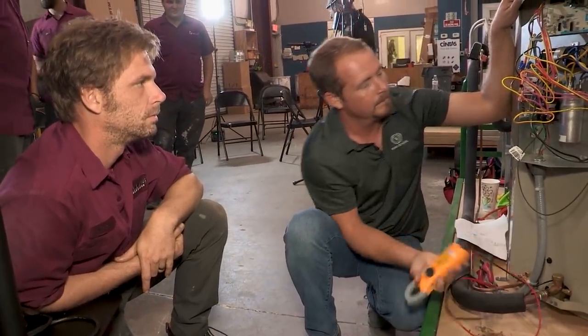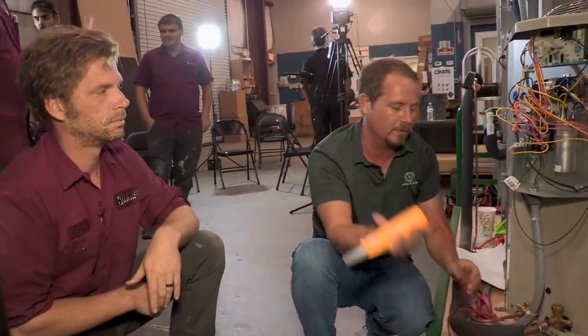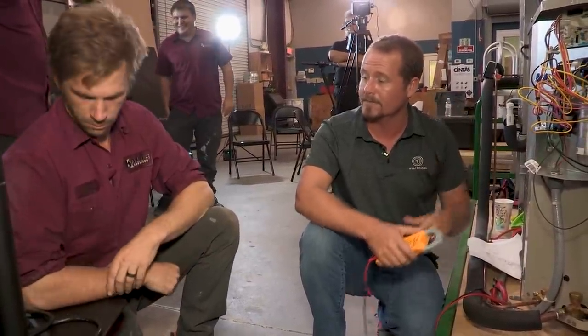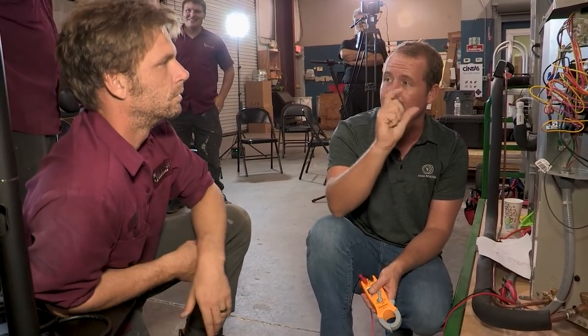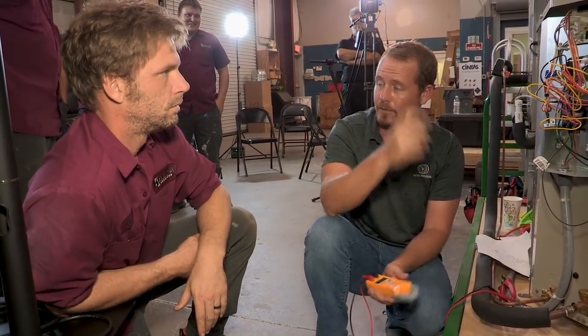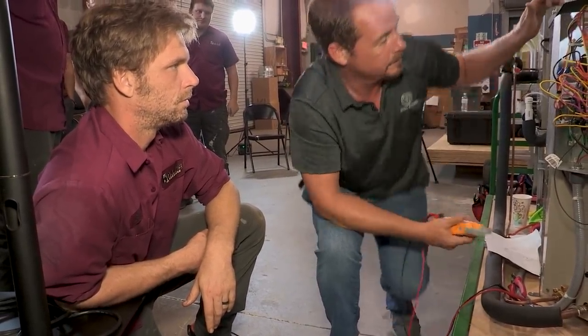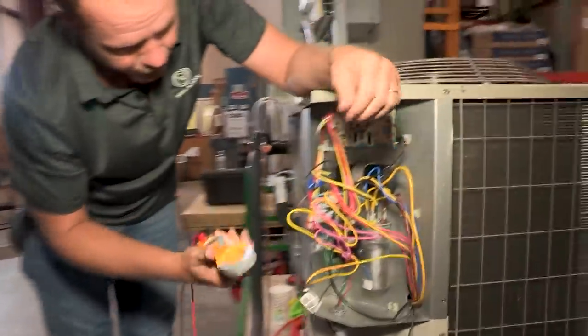Cool. So how would you test it? That's one question that people ask. You could test it by actually measuring your start amps with the capacitor in and without it in, either on common, and if you did it on common, then it would actually show lower start amps, not because the start amps actually are lower, but because the amount of time is lower, and so your meter will show it as lower. Or you could actually do it on your start winding going to your compressor.